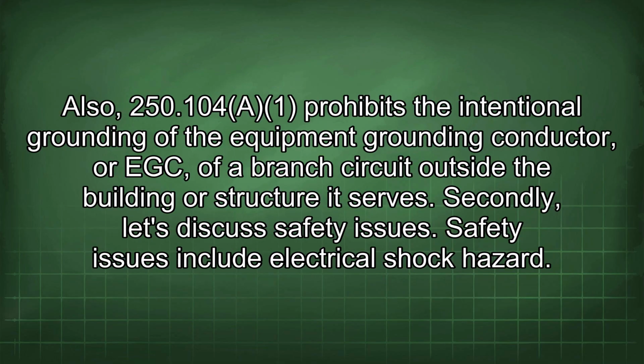Also, 250.104(A)(1) prohibits the intentional grounding of the equipment grounding conductor, or EGC, of a branch circuit outside the building or structure it serves. Secondly, let's discuss safety issues.